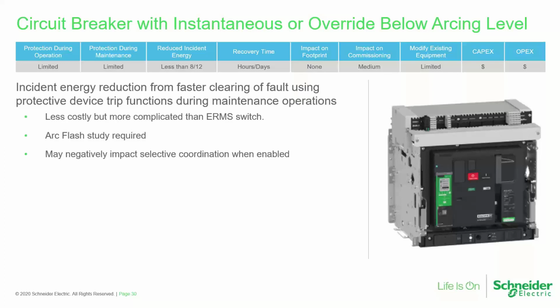And that may cause some problems with coordination, either upstream or downstream. It's something that requires a little more thoughtful study to make sure we get it applied correctly. But if you can, it's very low cost compared to some of the other solutions, and can be very effective. If you have a breaker that's tripping instantaneously, at least in the low voltage world, you can't make a breaker trip faster than instantaneous. So we've got pretty good protection there if the system layout and coordination allows us to do it.